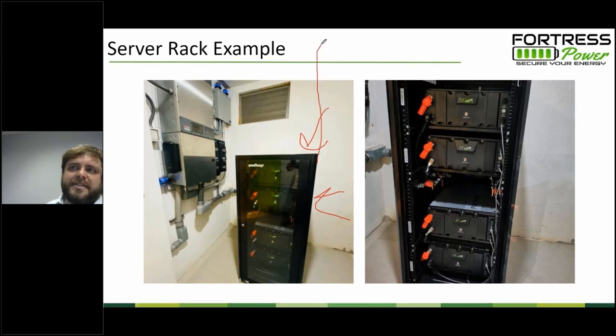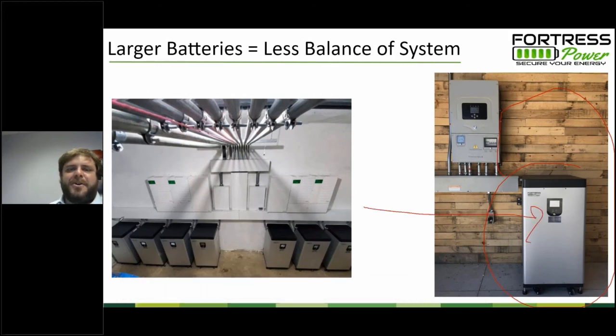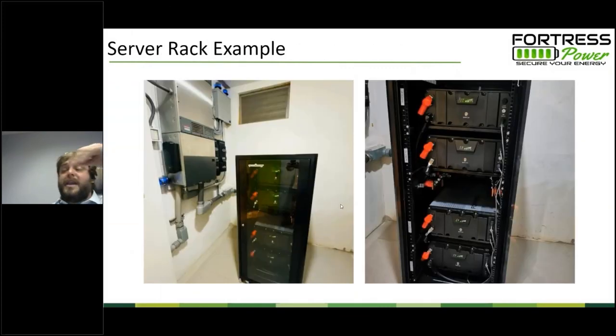Server racks make a lot of sense when you have a really tall server rack and you're doing a bunch of eFlexes, like in a commercial server room, or if you have the need for a server rack. The server racks are not for just holding batteries. They're for other kinds of server rack mountable equipment. So if you have the need for a server rack, it is a nice option. But don't discount the fact that 3 eFlexes in a small server rack is very similar in form factor to 1 eVault. And while the eFlex is a little bit ahead in terms of Wi-Fi and communication features, it is often a little bit more of a costlier install than just using the eVault.